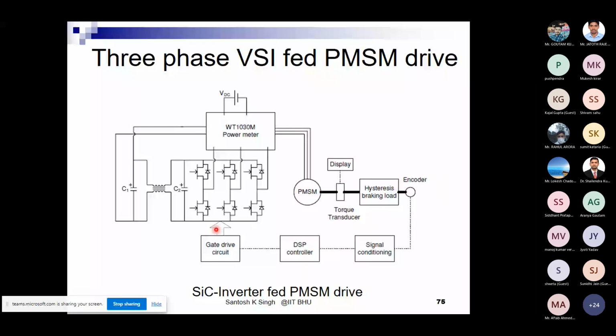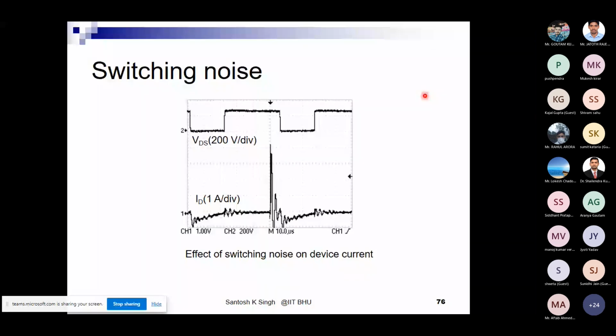In this case we also tried to get the values using Yokogawa make power meters. There were some issues with respect to switching noise. This was actually coming because, in the case of motor drive application, between two adjacent windings we have got some capacitance. That's what we call the interwinding capacitance. That interwinding capacitance was visible in this case, and it was creating problems.